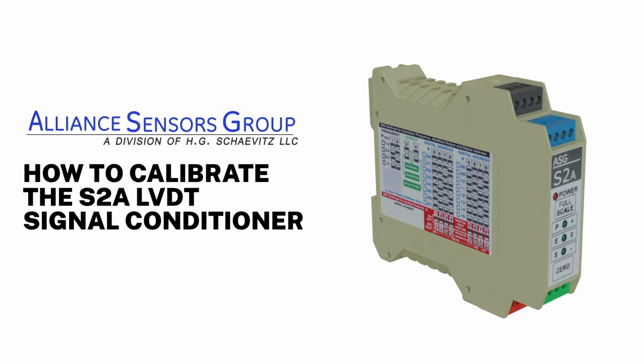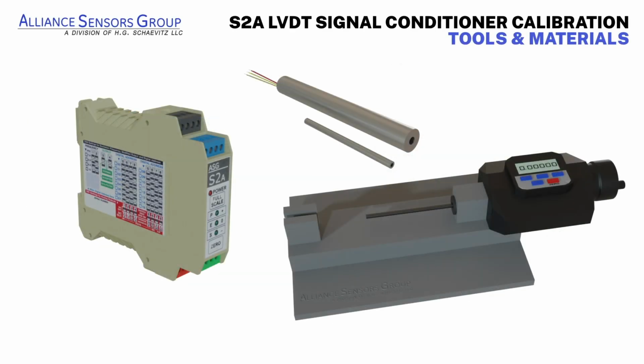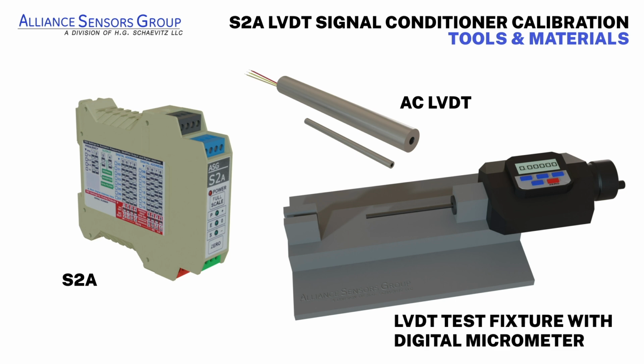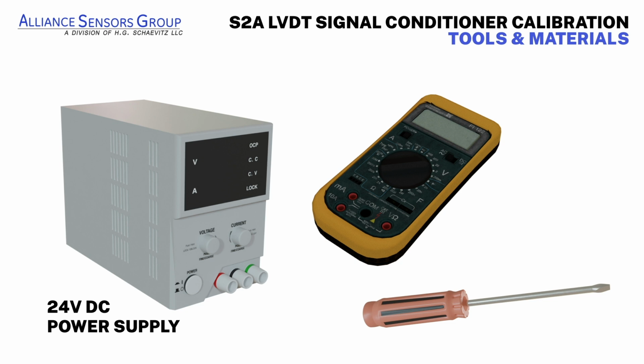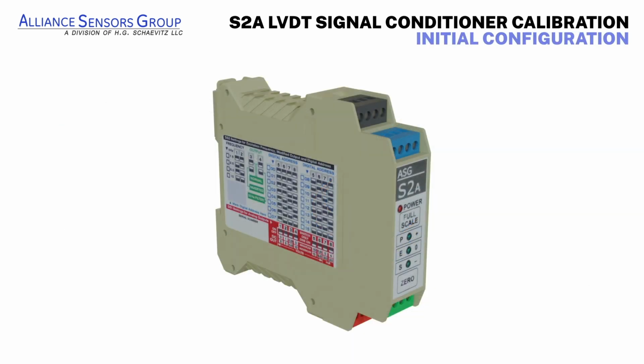In this video, we will demonstrate how to calibrate the S2A LVDT signal conditioner from Alliance Sensors Group. To perform this task, you will need the following: an S2A LVDT signal conditioner, an AC LVDT to be calibrated, an LVDT test fixture with digital micrometer, a 24-volt DC power supply, a DC voltmeter or digital multimeter, and a small screwdriver. The S2A's factory default settings are adequate for most standard industrial LVDTs, and no adjustments are typically required.